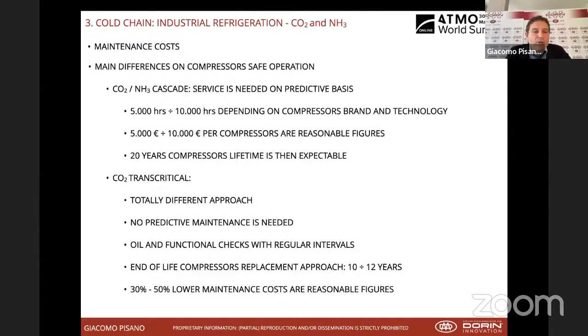While with CO2 transcritical, this is a completely different approach because, especially with compressors, like I said, there is no predictive maintenance needed. Clearly, oil and functional checks have to be done at regular intervals. Normally, compressors can be running until their end of life, so let's say 10 to 12 years, depending on the amount of hours of operation every day. And again, when it comes to maintenance cost, CO2 can bring in a significant cost saving that can be rated between 30% and 50% as reasonable figures. Clearly, it is very difficult to provide exact numbers.